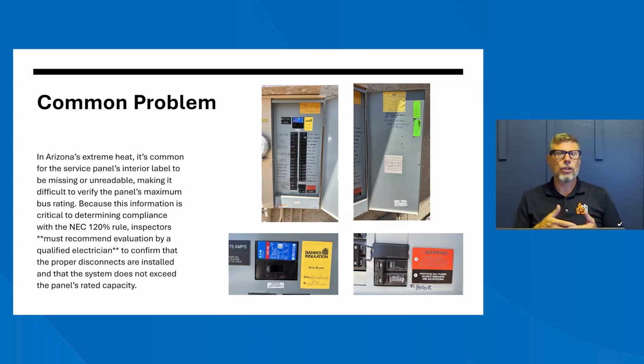So we want to make sure that we're looking for that. Make sure that there's a label. If you don't see the label, that is an absolute call out. You want to make sure that an electrician comes out, rates the panel, and makes sure that we have the right size breaker. They might still need to derate that breaker further. I would hope not, because under 75 is pretty low for our modern homes, but that is a chance.